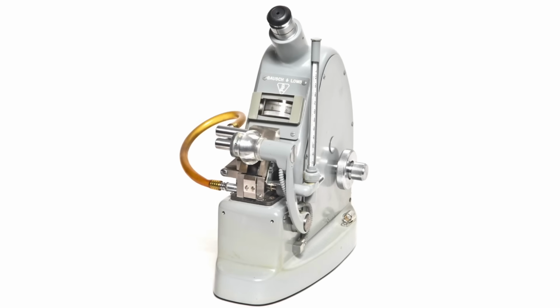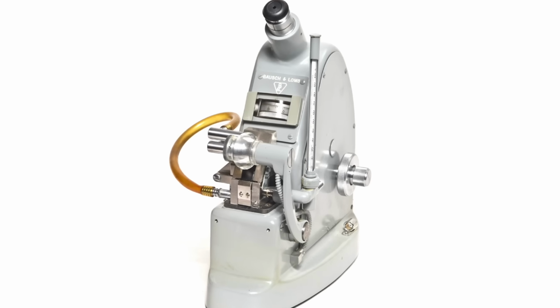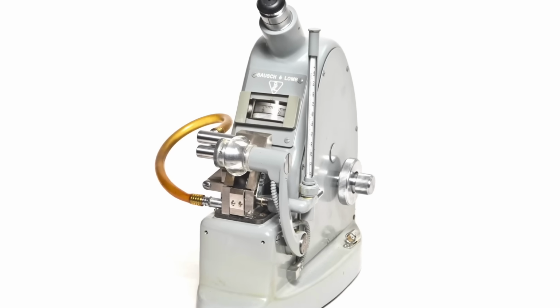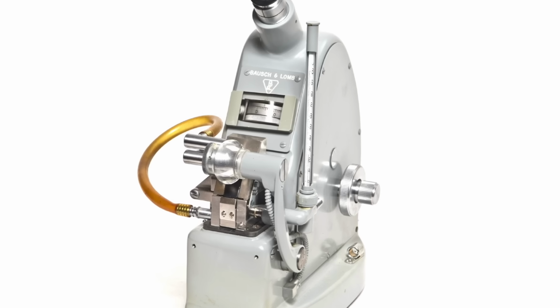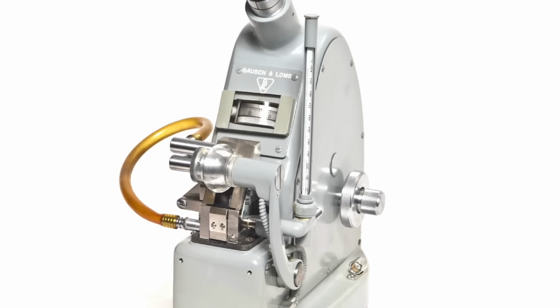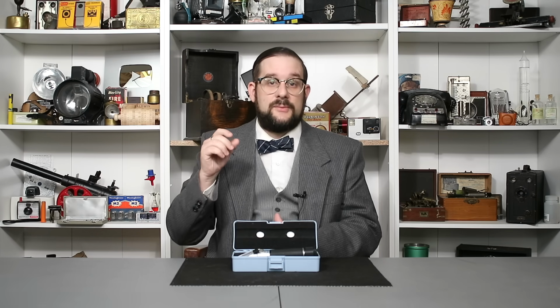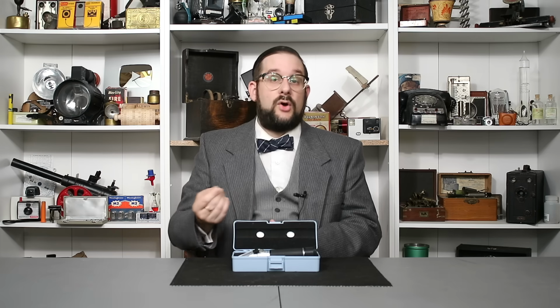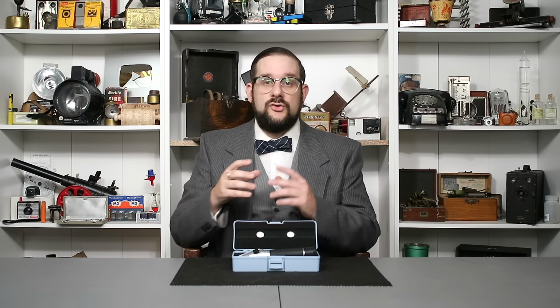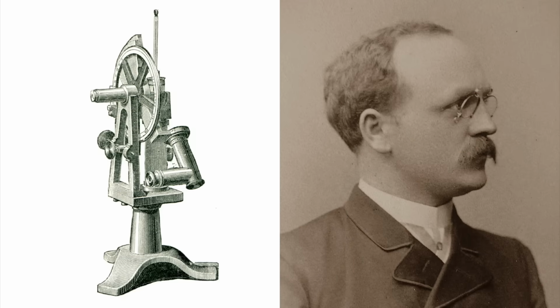Now, in early Abbe refractometers, the effects of temperature were compensated for by immersing the prism holder in a water bath with a thermometer, which stabilized the temperature and could be monitored and compensated for. Later versions had a bimetallic strip that would automatically adjust the lenses and prisms according to temperature, whereas modern versions will often have a thermoelectric cooling and thermostat system in order to maintain the prism within a certain range of temperatures.